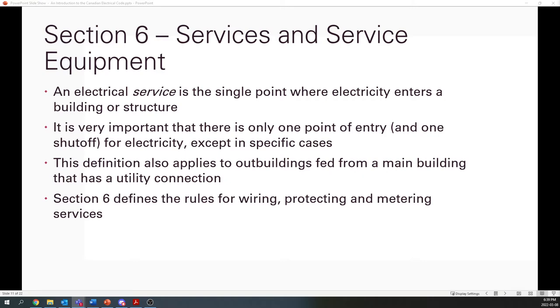If you have a house maybe in a slightly older area that has overhead distribution on your back lane, 120-240 volt overhead distribution, the service comes down off the hydro pole or the hydro line in your back alley, comes onto an attachment point on your house, and then it comes into the mast. And that is your service. That's your electrical service. You're getting served the electricity by the utility.